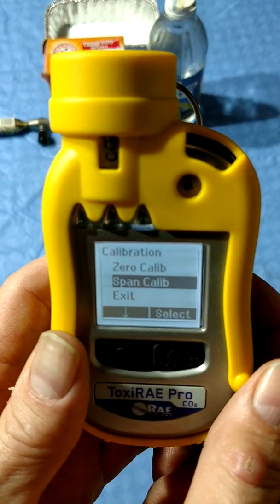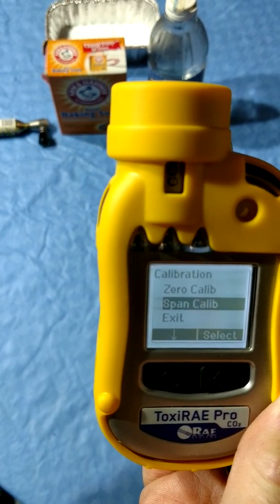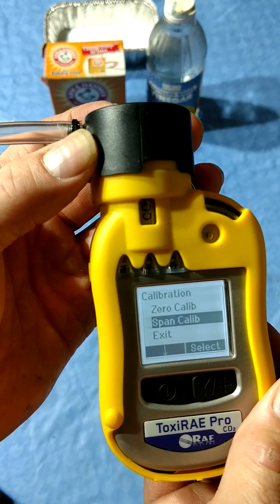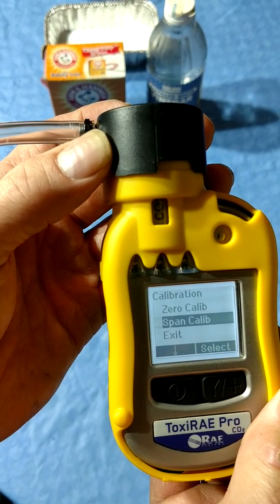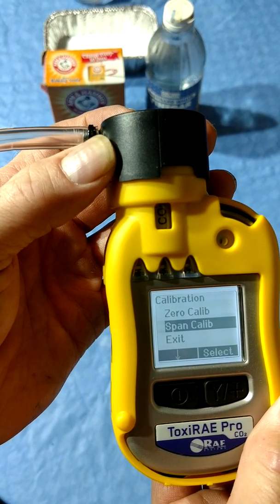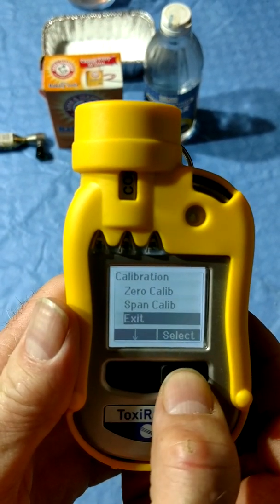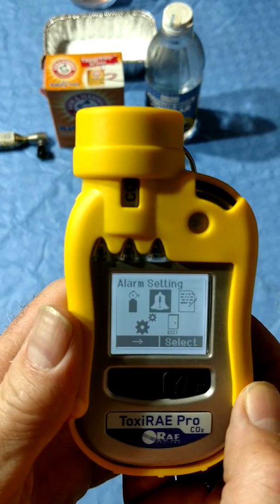To perform a span calibration, use this option. Place the calibration adapter on the meter and attach it to the cal bottle and the regulator. The regulator needs to be a fixed flow type with a flow rate between 0.5 and 1.0 liters per minute. The ToxiRAE is a diffusion meter, not pumped like the MultiRAEs. Do not use a demand flow regulator with the Toxirays. The other menus are alarm, data logging, and other settings.